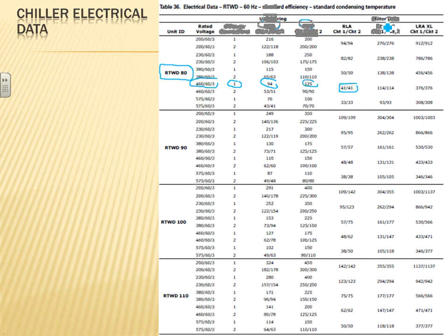As well as these, which are interesting. If you're starting your motor in a Y, the locked rotor current will be 114. If you start your motor across the line, which is a delta, your locked rotor current will be 374.6. Very interesting. That's why most chillers have a Y-delta start. They start as a Y, chop down the starting current to 114, and then reconfigure into a delta and get the full oomph out of this chiller. The delta gives you a lot of torque. I thought this is really interesting, directly from the manufacturer.